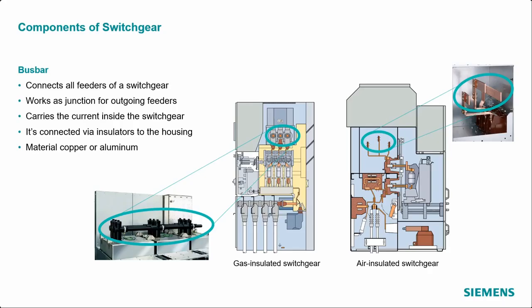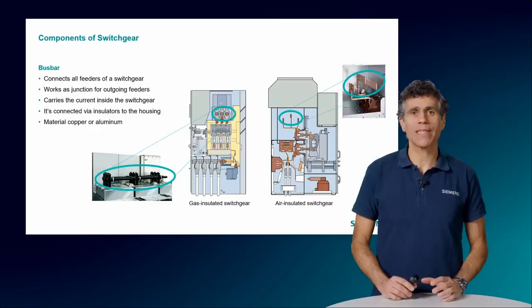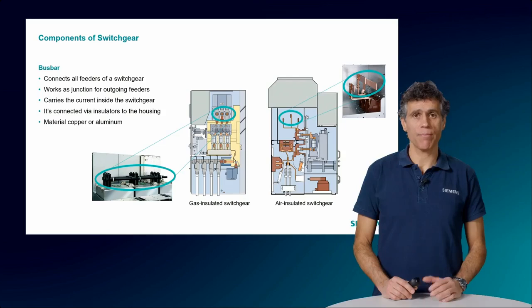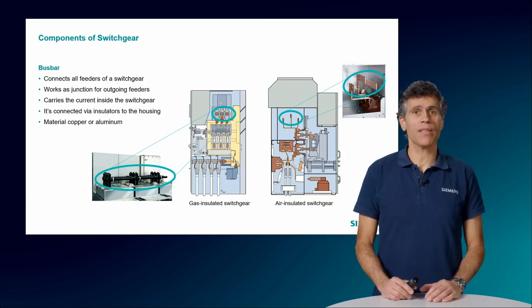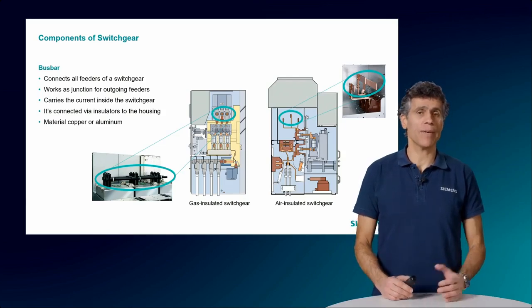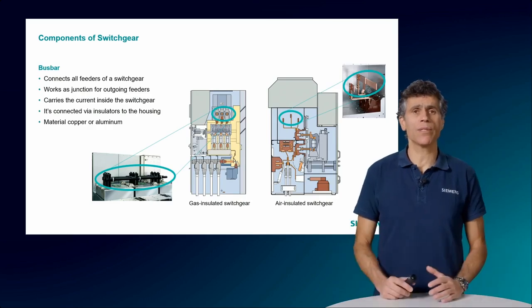Busbars are usually made of copper, but aluminium can also be used. In theory, any metal could do the job because it's about transporting electrical current, but copper is usually the best choice for this and therefore the most common. The busbar must be sustained via insulators so that the outside of the switchgear, meaning whatever a person can touch, is always grounded and not dangerous. By the way, this applies to any component that is connected to voltage, also at our homes, computers, mobile phones.